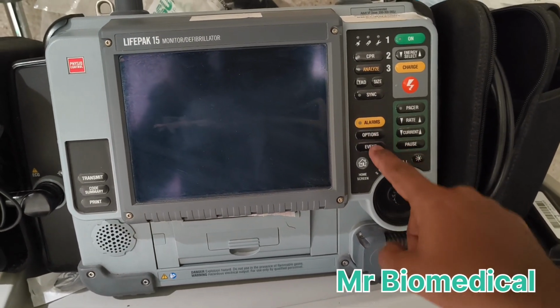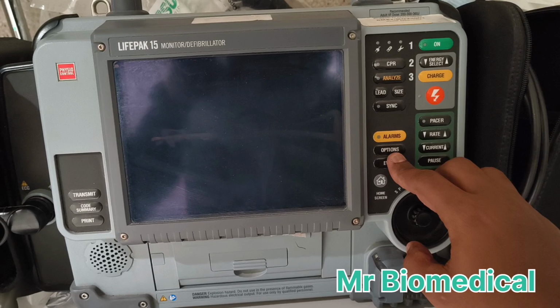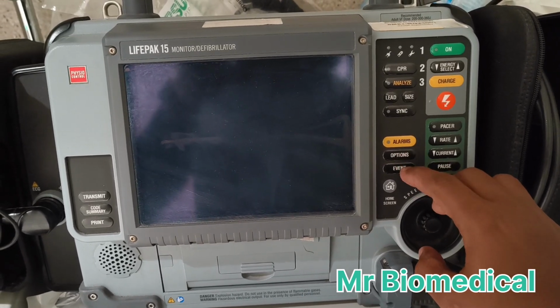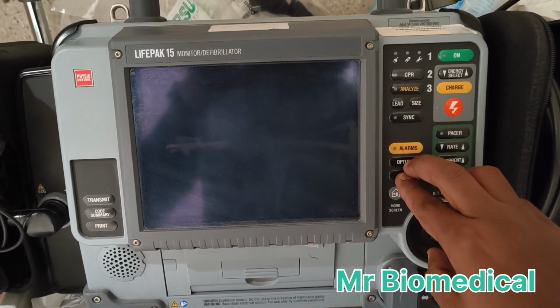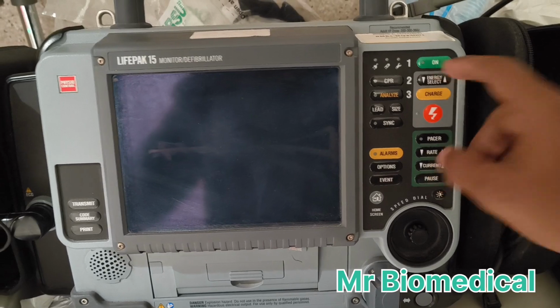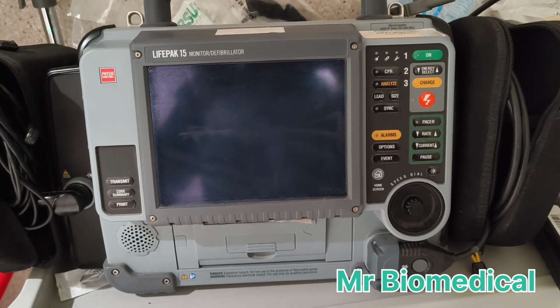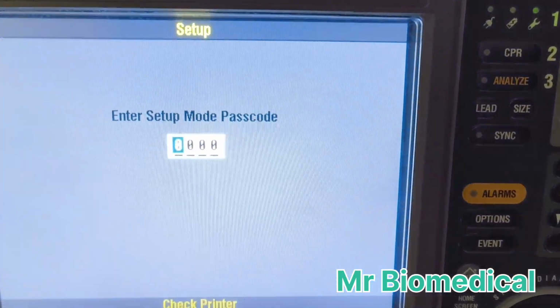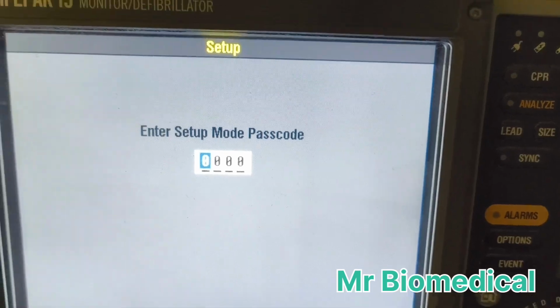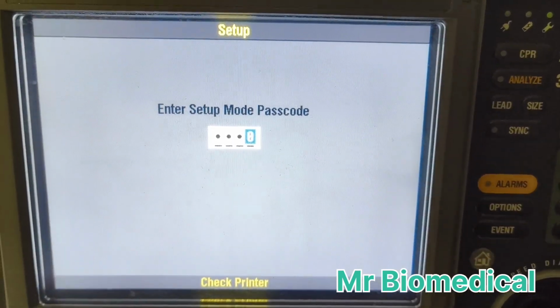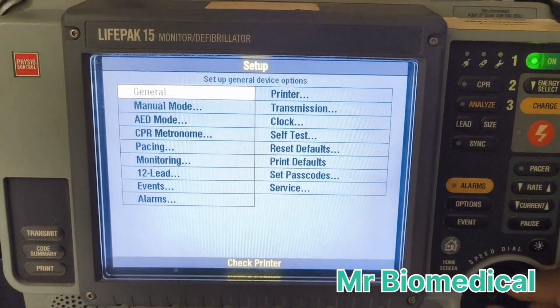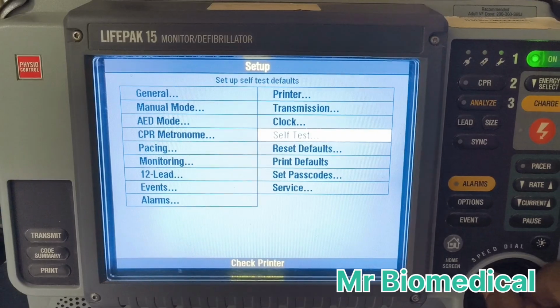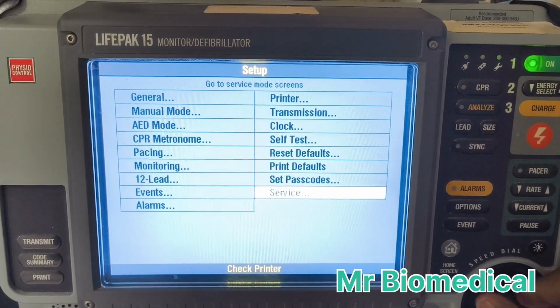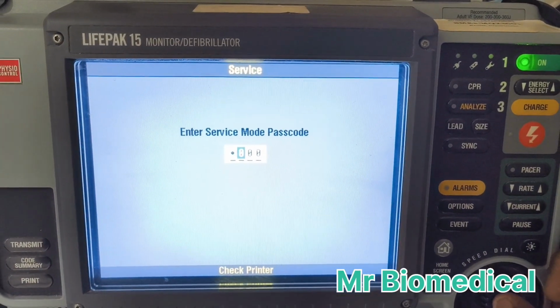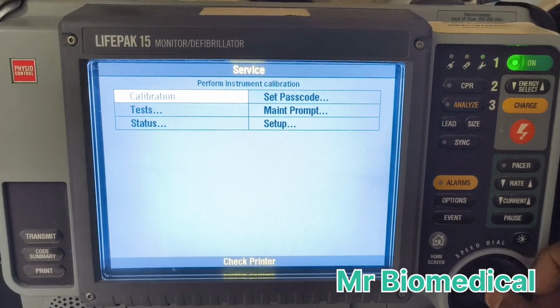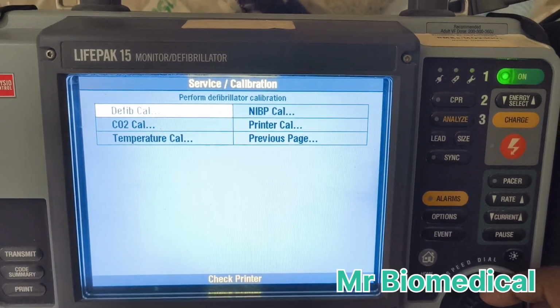For this you have to hold the options and event buttons and then press the power on button. So hold options and event and then switch the power on. And you can see it will enter the service mode, and the password is 0000, and go to the service, and that also is 0000, and calibration.